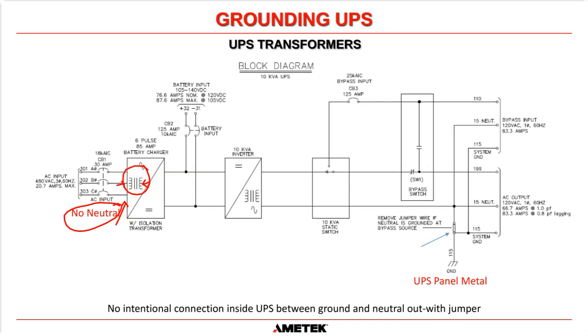But you also notice on the output of our system, this is the inverter. The inverter has an isolation transformer, which once again has isolation between the primary and the secondary. Okay, so you can now see from this drawing that these are connected back to your MCC. There is no electrical connection between this output here, the live and the neutral, with respect to the MCC 480 volt feed into the UPS. Okay, we have to actually create a grounding system for you to comply with electrical code.